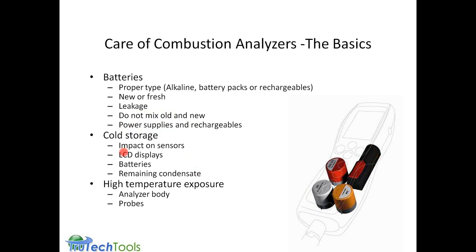same time. We talked about cold storage and the impact on the condensate, but it also has an impact on making the LCD displays a little sluggish and slow to respond. That's usually not a permanent failure or defect. They'll come back after they warm up a little bit. Batteries too can have a little bit of depressed performance when they're very cold. Again, you don't have to baby the meter necessarily, but do take it in when it gets very cold.